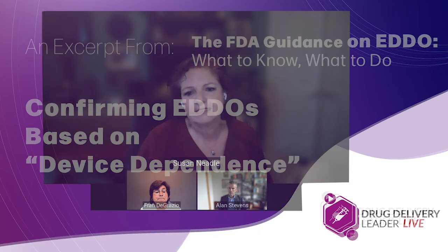So, versus now if you flipped over and talked about an auto injector, you can say, well, I'm putting it straight onto my thigh or my arm. And as I'm administering that product, now it's design dependent. The way it's going to sit on my skin, right, is design dependent. So it's specifically tied to the device. So you have to be able to do that assessment product type by product type, and based on its intended uses and what's in the IFU to figure out whether those features are device dependent versus dependent on something outside of just the device design, like a human being.